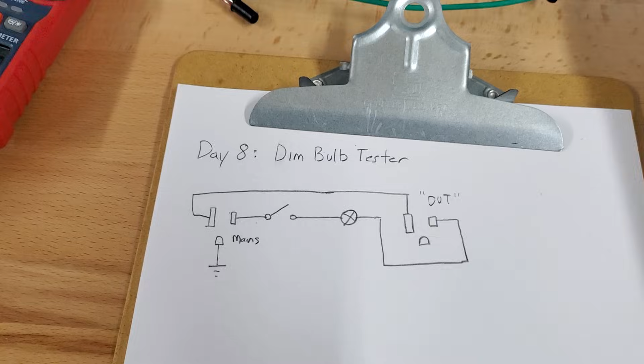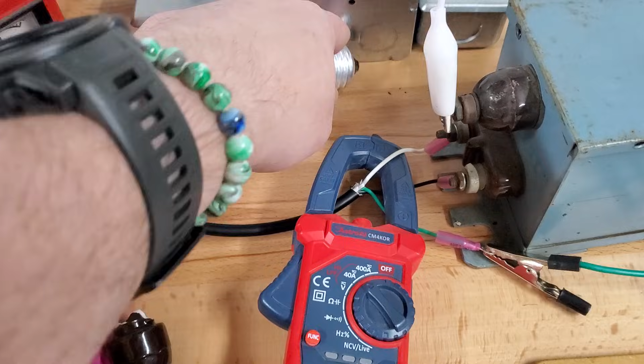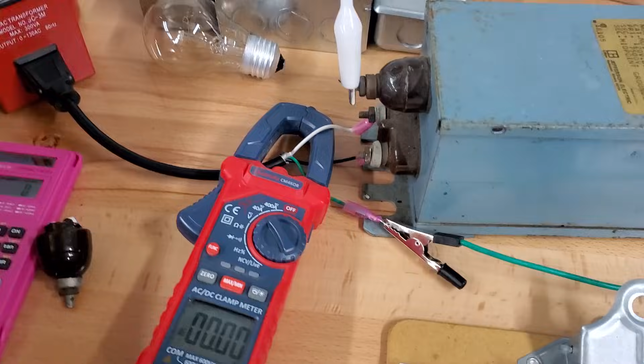What I probably should have done, if I built it again, is bring a loop of neutral out through one of these ports here, to let you put a clamp meter on it, or even build a current and voltage measuring device into it. That would be handy. For a deluxe version, you could get one of those little current transformer and voltage power meters, like I have for the power in this entire lab, and put one in the box, or use a Kill A Watt meter or similar off-the-shelf power measuring device in series.